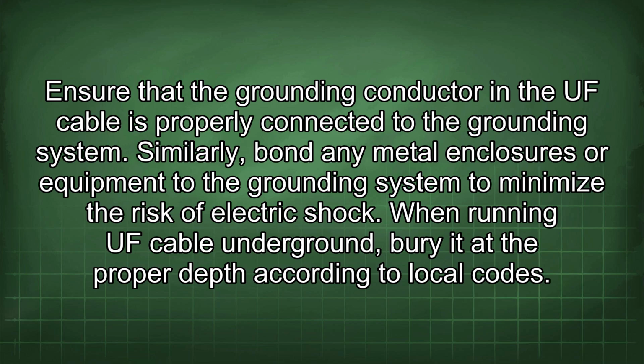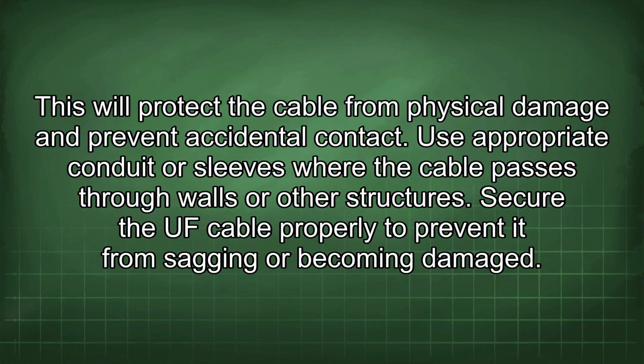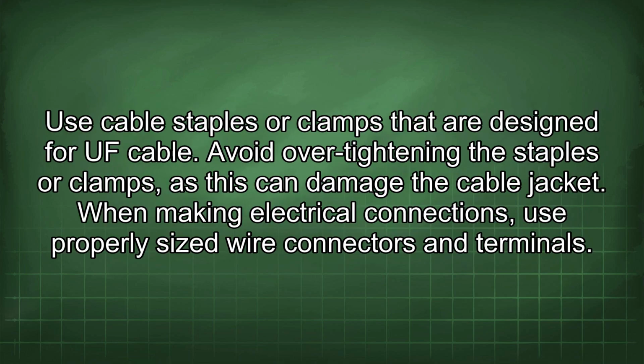When running UF cable underground, bury it at the proper depth according to local codes. This will protect the cable from physical damage and prevent accidental contact. Use appropriate conduit or sleeves where the cable passes through walls or other structures. Secure the UF cable properly to prevent it from sagging or becoming damaged. Use cable staples or clamps that are designed for UF cable.